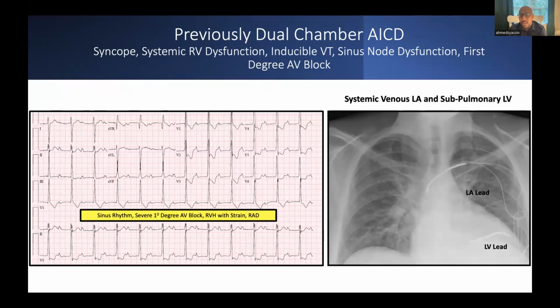So that's another issue that one has to care about. The VDD-like mode can be done by the Micra, where it detects the atrial mechanical signals and still achieves some AV synchrony, but that is limited. It only goes up to a certain heart rate. That's right. And it has a lot of issues when you turn that on. Sometimes in sinus rhythm, it starts pacing without that. So it is very limited, especially in a young patient where you want tracking. If he develops true AV block, you want him to track up to 140, 150. And this is a young guy. So that you won't be able to do with the Micra that we have now. Absolutely, it's a very good point.